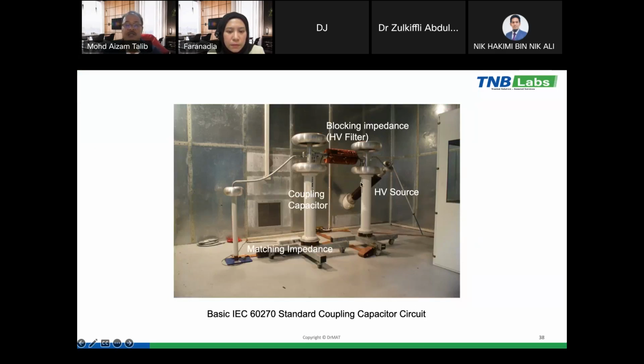Okay, here you have seen the video. Here is the HV source, and then we have a blocking impedance or HV filter. We have a coupling capacitor, and then here we have a matching impedance, or sometimes we call it a quadrupole. So from this matching impedance, it will be connected to the measuring instrument in the control room.